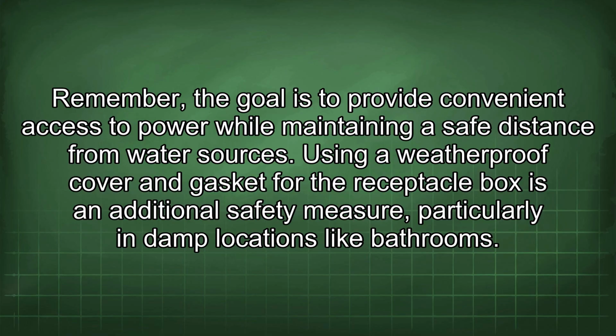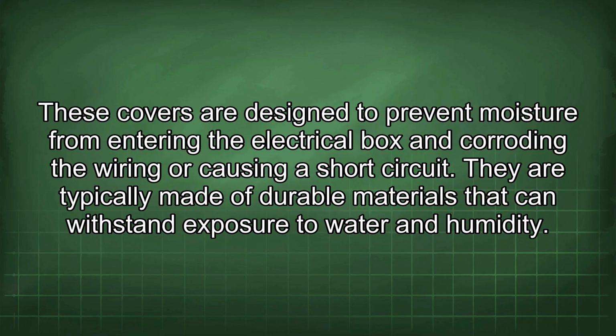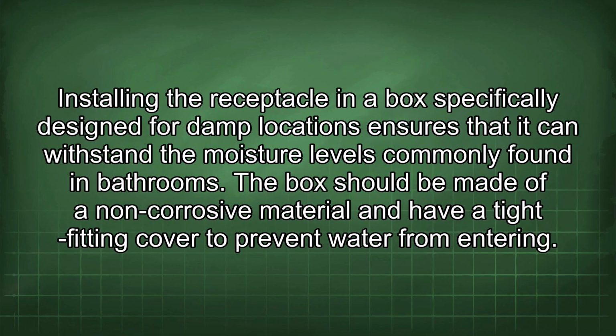Using a weatherproof cover and gasket for the receptacle box is an additional safety measure, particularly in damp locations like bathrooms. These covers are designed to prevent moisture from entering the electrical box and corroding the wiring or causing a short circuit. They are typically made of durable materials that can withstand exposure to water and humidity. Installing the receptacle in a box specifically designed for damp locations ensures that it can withstand the moisture levels commonly found in bathrooms.